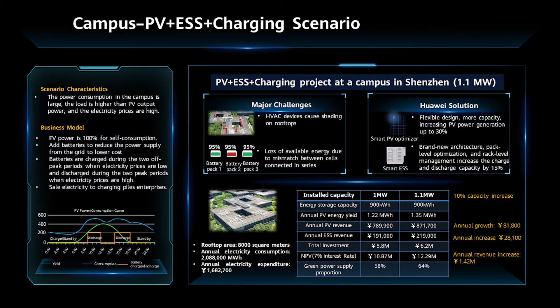So what if there's a high demand for electricity in the campus? The load is obviously higher than the solar power generation, and the electricity price is high. Let's learn about the solar storage charging scenario. Here is a case of the Huawei Shenzhen campus. The rooftop of this campus is 8,000 square meters, and the initial configuration of the project is 1 megawatt solar and 900 kilowatt hour energy storage. And Huawei optimizers are used to avoid the shadow of the HVAC devices on the rooftop. And more than 10% more power is generated by installing the optimizers.